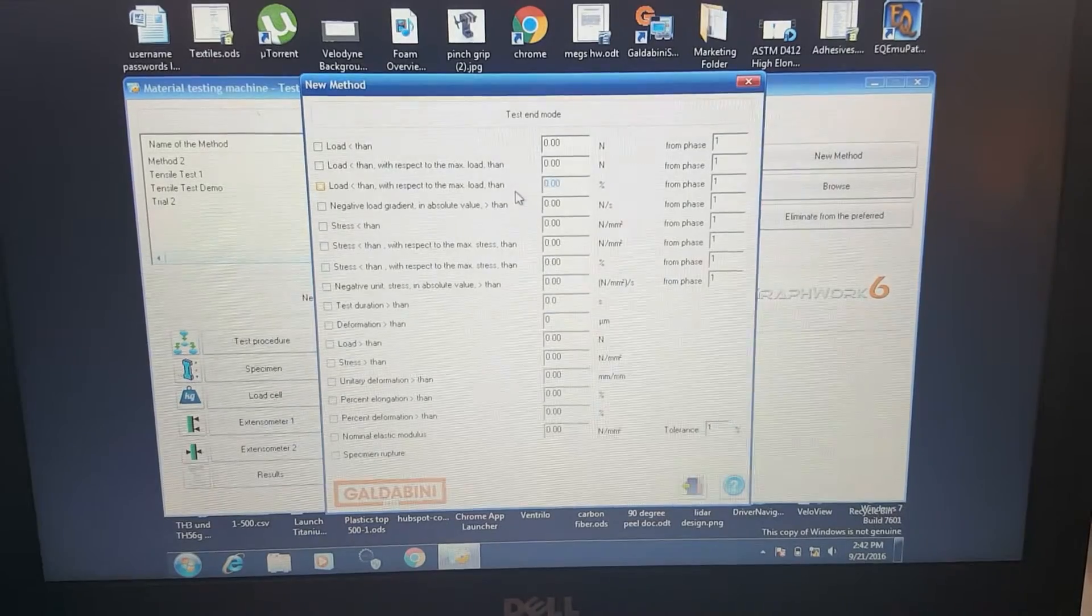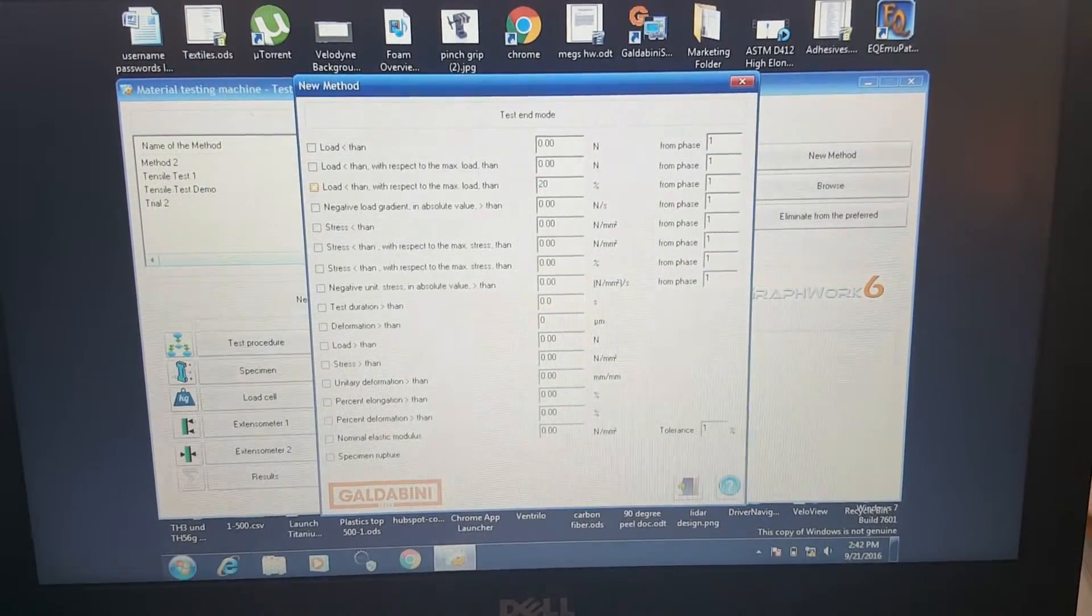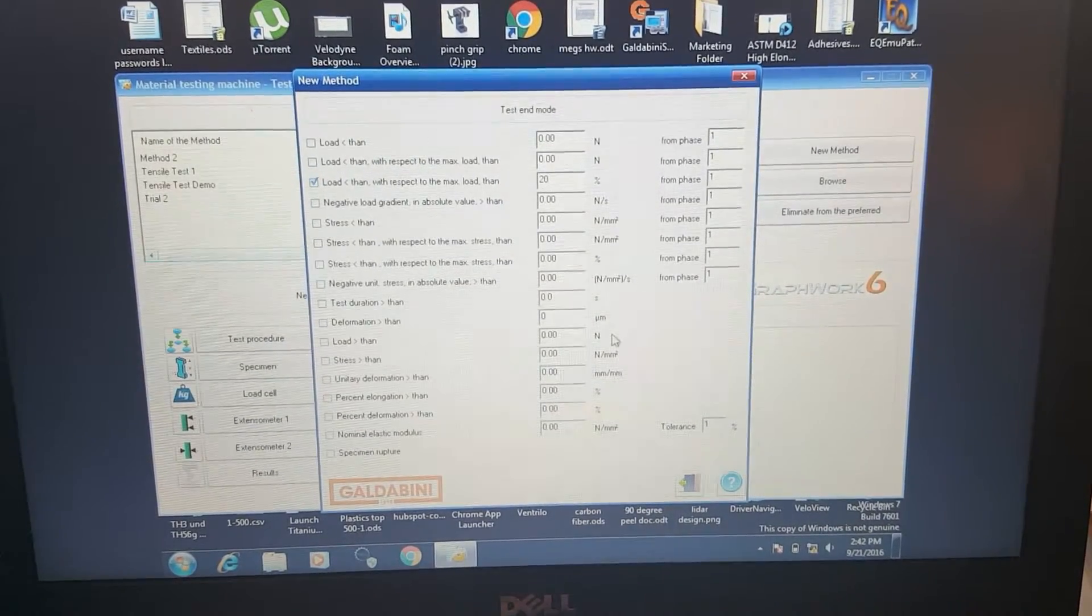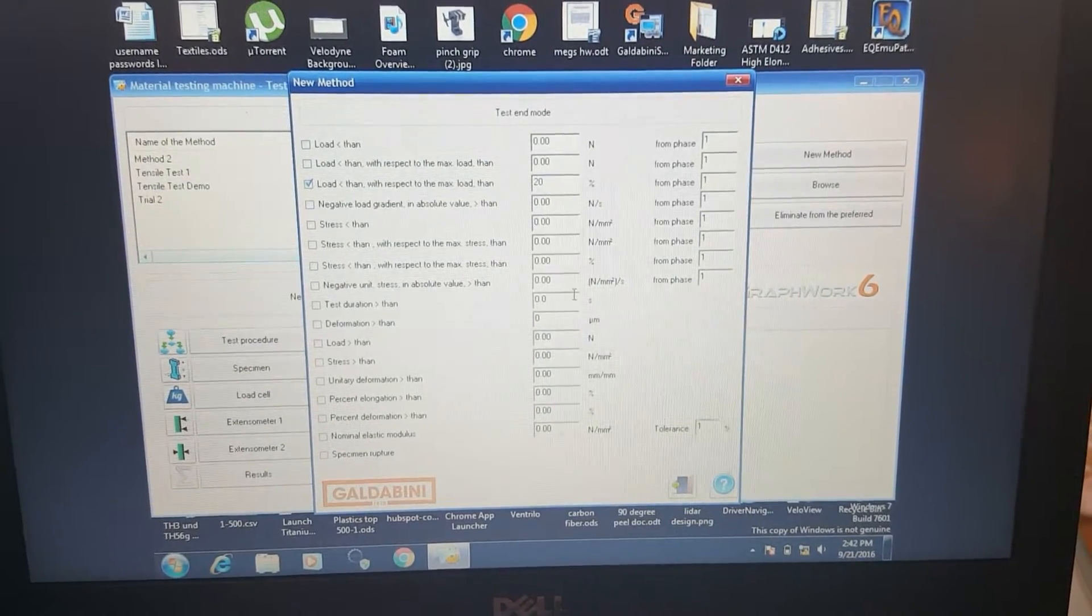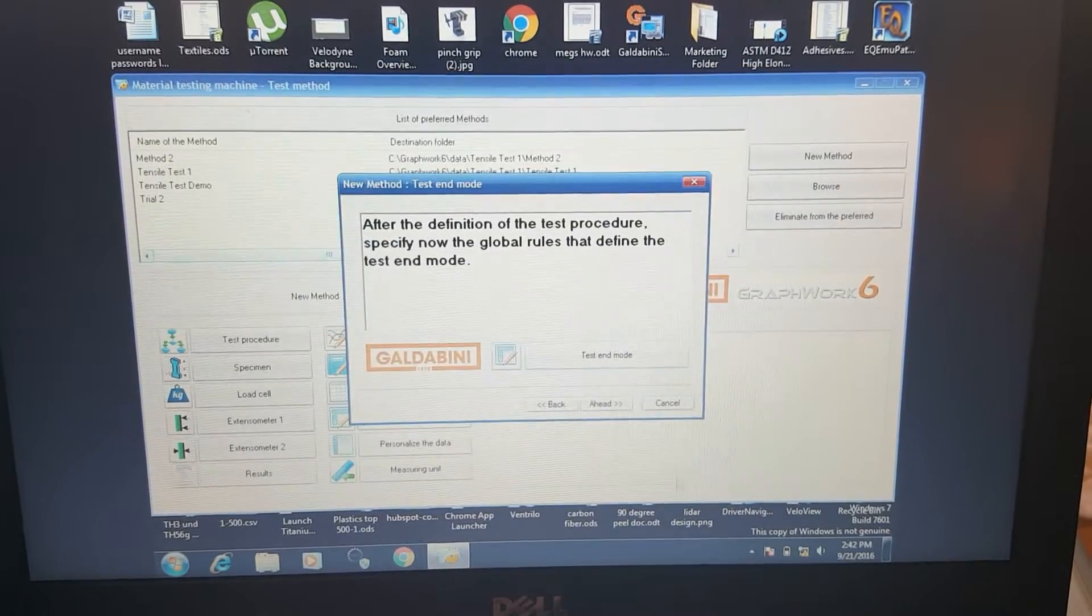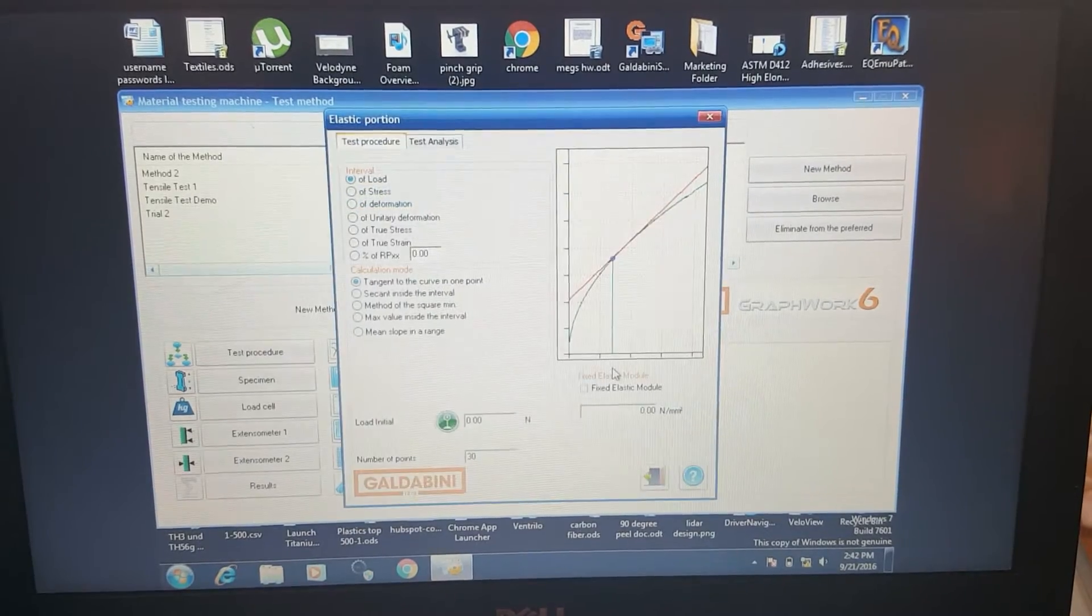Here we can define the test end mode. We can set a percentage off the drop of the max load. I usually like to set at 20%. This is the one that most people use. But there's a bunch of different definitions we can set to stop the test procedure at the end of the test.